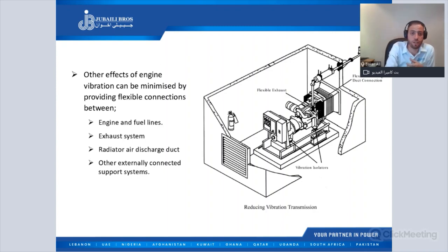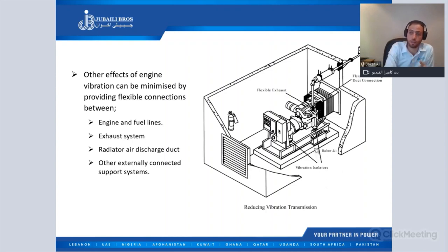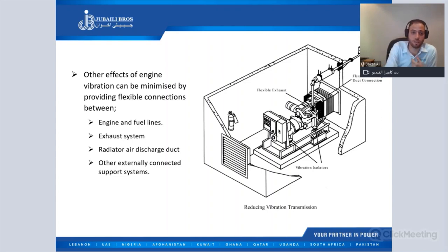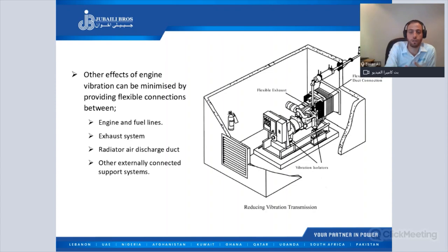Other effects of engine vibration can be minimized by providing flexible connections between the engine and fuel lines, to avoid vibration transmission from the engine to the steel fuel lines and to avoid any damage. For the exhaust system, we fix flexible bellows to avoid vibration transmission from the engine to the exhaust system. For the air discharge duct, we fix a flexible duct connector to avoid vibration transmission to the wall and to the building.